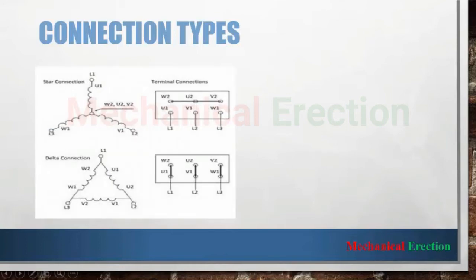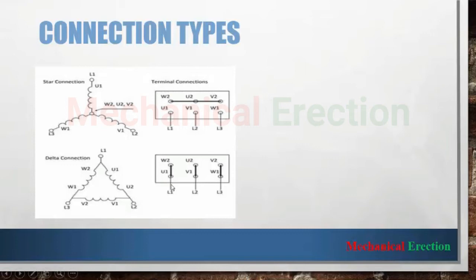Next are the connection types of a motor. There are basically three types for three-phase induction motors. First is star connection, in which one end of each winding is connected to a supply phase while the other end of each winding is joined together to form a star. Then delta connection — in delta connection, all six ends of the three windings are supplied by incoming voltages. Delta is mainly needed for high torque applications where high starting current is required.